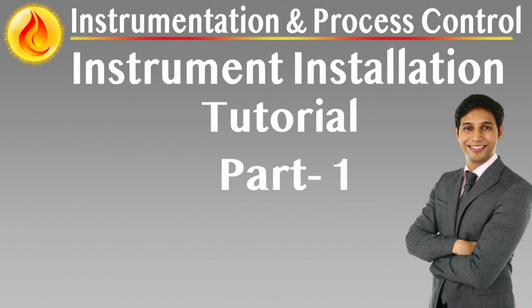Filling, flushing, venting, and draining, engineered access for safe maintenance and process integrity, controlled access for fluid handling and isolation. Impulse line designs must incorporate dedicated provisions for filling, flushing, venting, and draining to support safe maintenance and to ensure measurement reliability in the presence of aggressive, toxic, or high-viscosity fluids. These provisions must allow controlled handling of both process and seal fluids without exposure risk to personnel or the environment. Where the removal or replacement of seal or process fluid poses a hazard or contamination risk, flushing and neutralizing must be possible before any disconnection occurs.